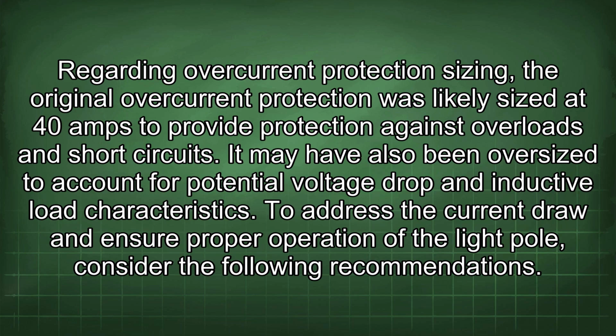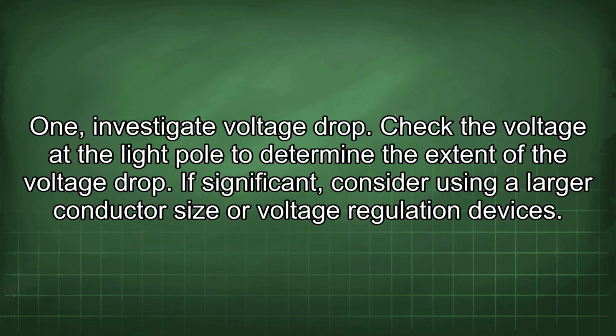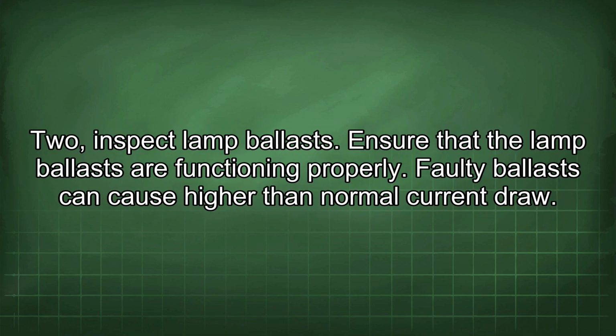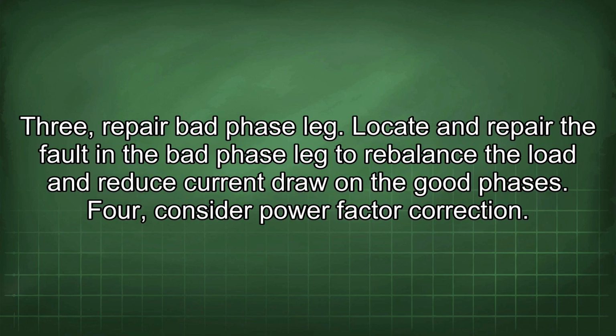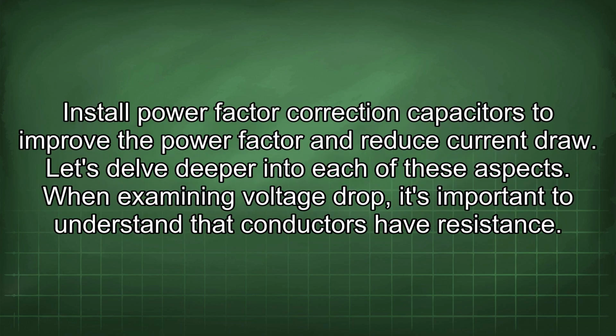To address the current draw and ensure proper operation of the light pole, consider the following recommendations. 1. Investigate voltage drop. Check the voltage at the light pole to determine the extent of the voltage drop. If significant, consider using a larger conductor size or voltage regulation devices. 2. Inspect lamp ballasts. Ensure that the lamp ballasts are functioning properly. Faulty ballasts can cause higher than normal current draw. 3. Repair bad phase leg. Locate and repair the fault in the bad phase leg to rebalance the load and reduce current draw on the good phases. 4. Consider power factor correction. Install power factor correction capacitors to improve the power factor and reduce current draw.